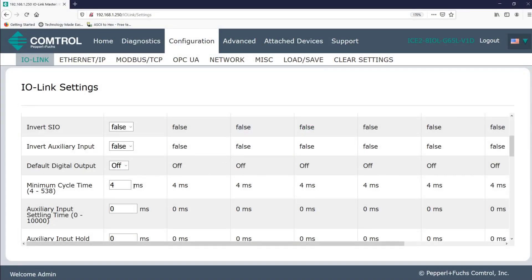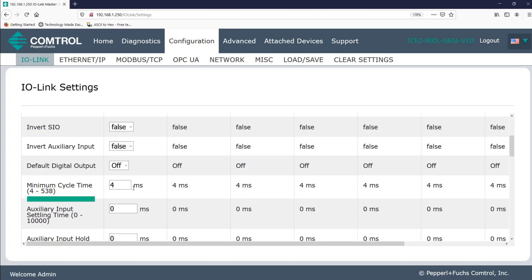Next, we see the minimum cycle time, which lets us configure how often data will be sent between our device and the IO link master, the default value being every four milliseconds. You can program this anywhere from four milliseconds up to 538 milliseconds. If you do leave the minimum cycle time set to the default value, the IO link master will negotiate with the IO link device for its minimum cycle time. And you can see this on the diagnostics page displayed as the actual cycle time.